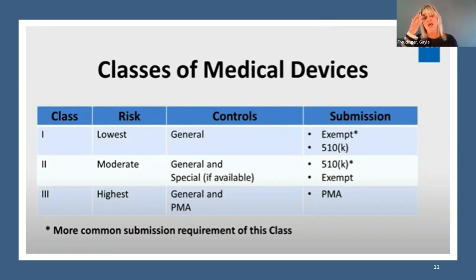It's recommended that you go to a particular database that the FDA has set up, and it's called accessdata.fda.gov. And again, that will be in the resource list, so that you can see all the medical devices that are listed and their associated classifications, product codes, and the FDA pre-market review organizations and other regulatory information. When you're determining which category your device should go into, you're going to want to look and see where other similar devices have fallen and look up their product code. So this will be a very important resource for you.